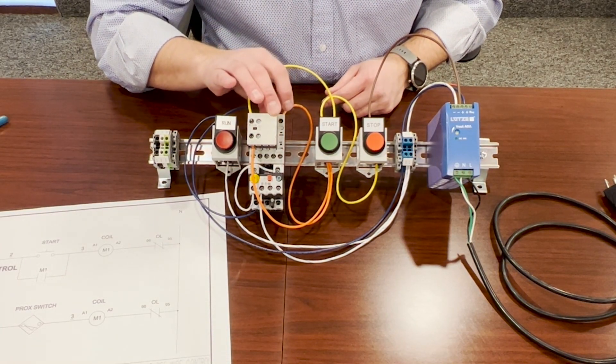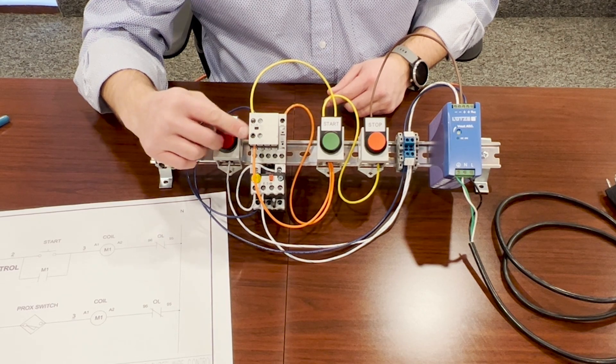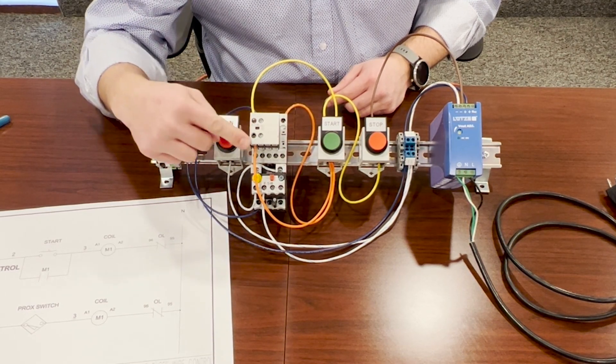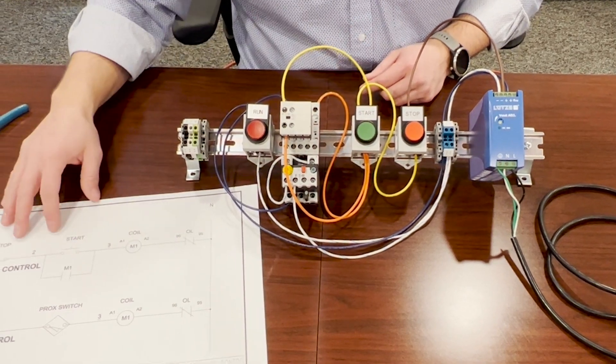So when this motor starter is energized, this contact that's normally open, it's going to close. And when it closes, it's basically going to bypass the start button and show that on a drawing.